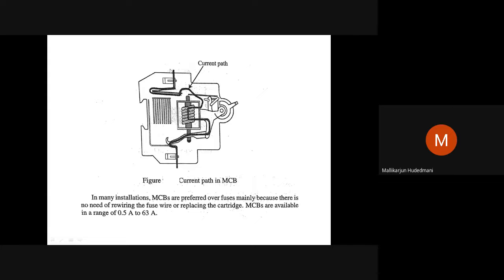The dark line which is shown is the incoming current path. Then through this device, it goes through the solenoid coil. It comes out to the bimetallic strip. It is called a bimetallic strip. Then to the lead outlet taken out. And this has a rack and pinion like mechanism, which has a knob to force it on. Suppose this lever is on, and if the bimetal strip operates, the bimetallic strip bends, deforms, this is going to open the contact. There is a contact established here.